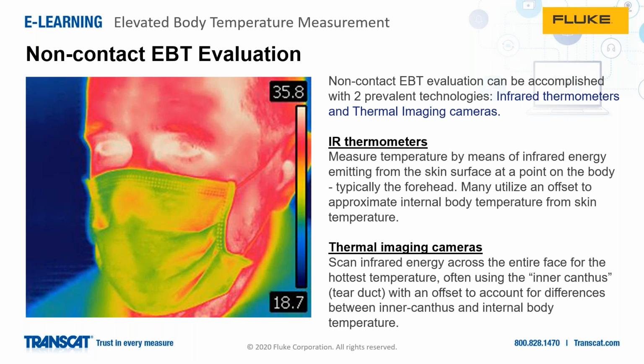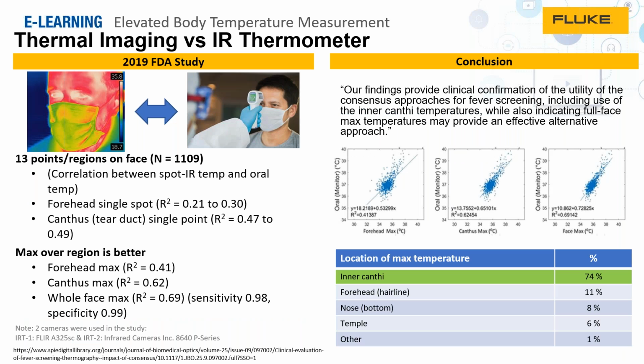With the IR thermometers, temperature is measured by essentially taking an IR measurement. All objects above essentially absolute zero give off IR radiation, and we can tie that with a correlation to temperature. So IR thermometers use a spot measurement on the skin with some sort of offset to try and determine your internal body temperature from your skin temperature. And then with this picture on the left, this is a thermal imaging camera. It's essentially a 2D infrared scan across the entire face, where they're often using the inner canthus, or the inner eye tear duct area, again with some sort of offset to try and determine body temperature from your outside skin temperature.